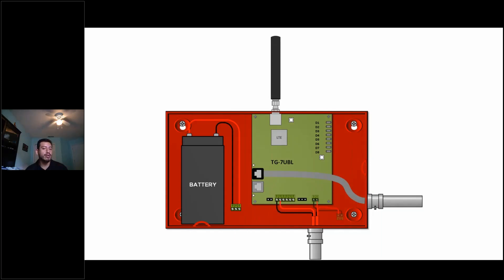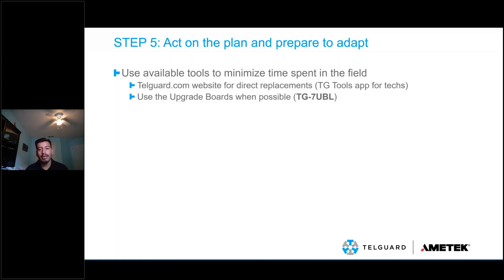The one thing I want to make sure we emphasize here is the antenna. The antenna is different — it's an LTE antenna that comes with the TG-7UBL, and it's a different antenna than what was used for 3G or CDMA. A lot of the time, particularly in a commercial application with an external antenna, or even just the same antenna extended with 12 feet of cable, we sometimes forget that the antenna needs to be replaced as well. Make sure you check that antenna and replace it with an LTE antenna, or if it's an external or high-gain antenna, it needs to be replaced with an equivalent.